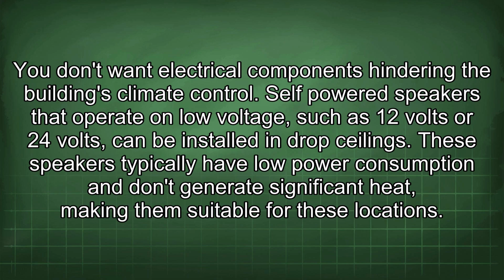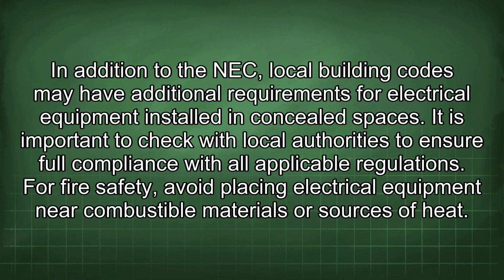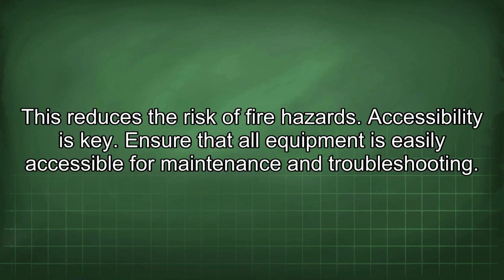Self-powered speakers that operate on low voltage, such as 12 volts or 24 volts, can be installed in drop ceilings. These speakers typically have low power consumption and don't generate significant heat, making them suitable for these locations. In addition to the NEC, local building codes may have additional requirements for electrical equipment installed in concealed spaces. It is important to check with local authorities to ensure full compliance with all applicable regulations. For fire safety, avoid placing electrical equipment near combustible materials or sources of heat. This reduces the risk of fire hazards.